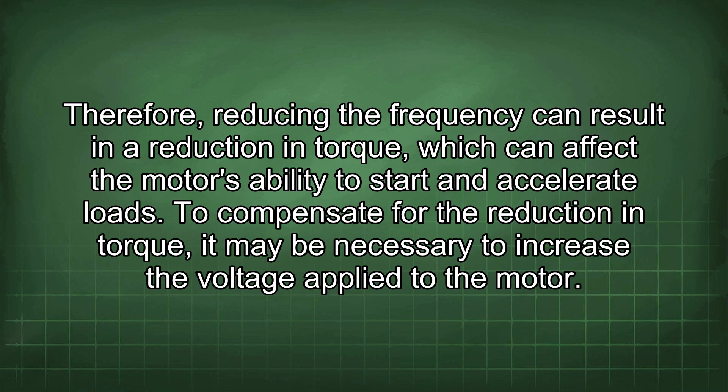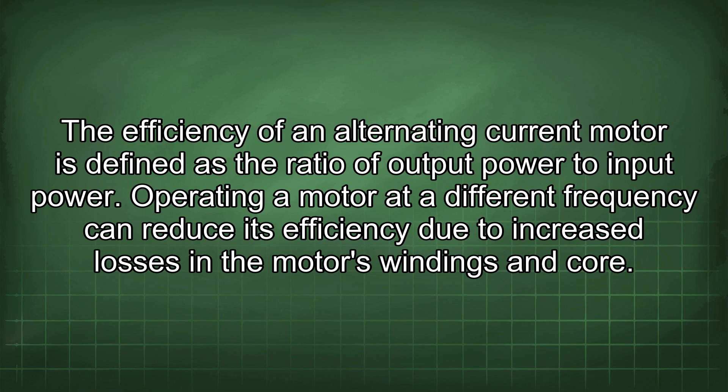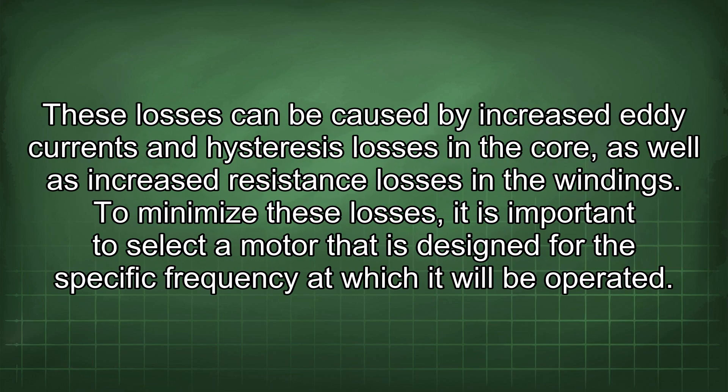To compensate for the reduction in torque, it may be necessary to increase the voltage applied to the motor. However, it is important to ensure that the voltage does not exceed the motor's rated voltage, as this can lead to overheating and damage. In addition to effects on motor speed and torque, operating a motor at a different frequency than its rated frequency can also affect its efficiency. The efficiency of an AC motor is defined as the ratio of output power to input power. Operating a motor at a different frequency can reduce efficiency due to increased losses in the motor's windings and core, caused by increased eddy currents, hysteresis losses, and increased resistance losses. To minimize these losses, it is important to select a motor designed for the specific frequency at which it will be operated.